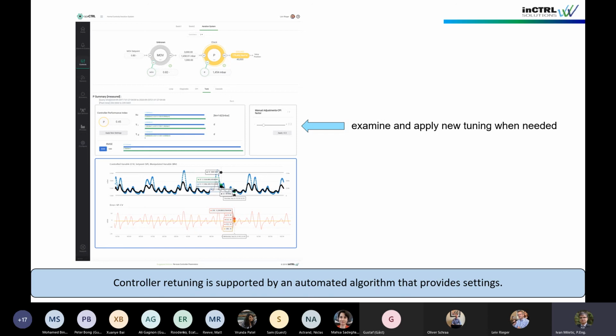At a button push, we can send the controller tuning parameters down into the DCS from the software so they can be applied in the controller, and then you can continue monitoring its performance over time after tuning.